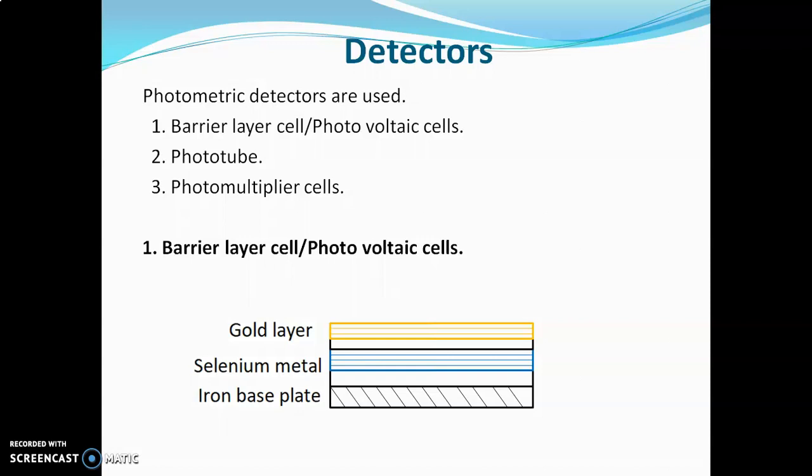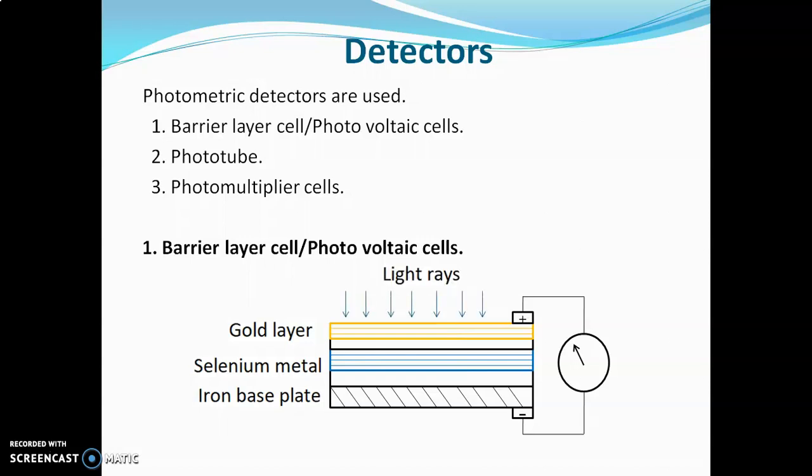Three metal layers are present in the barrier layer cell. When radiations hit the surface of the gold layer, electrons are generated at the interface of gold and selenium. These electrons are attracted towards the gold anode, causing current to flow through the external circuit. This amount of current is measured by a galvanometer, and is directly proportional to the radiations hitting the detector. It is a simple detector used in inexpensive instruments.